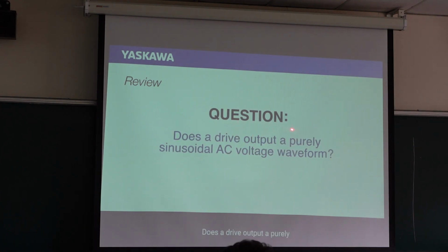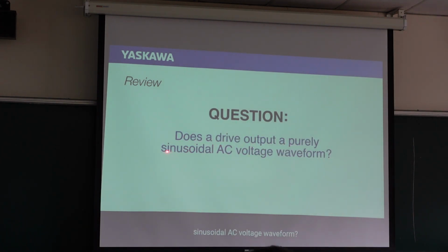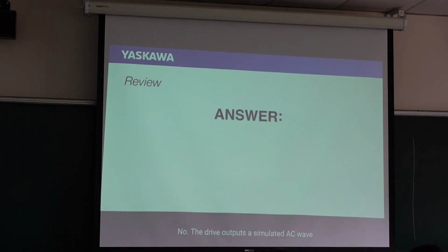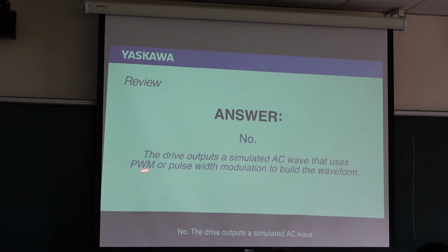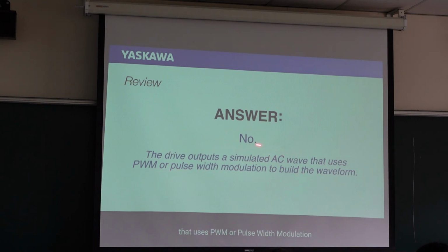Question number 3. Does a drive output a purely sinusoidal AC voltage? No. The drive outputs a simulated AC wave, not a real AC, that uses PWM, or pulse width modulation, to build the waveform.